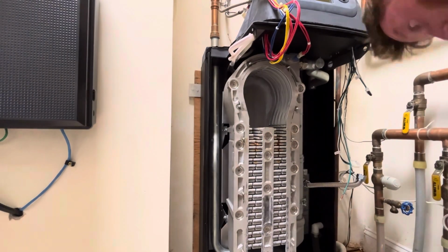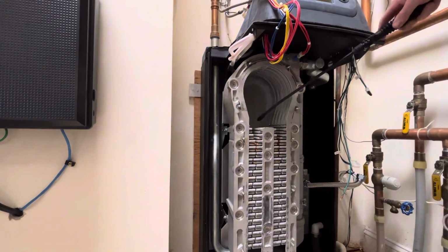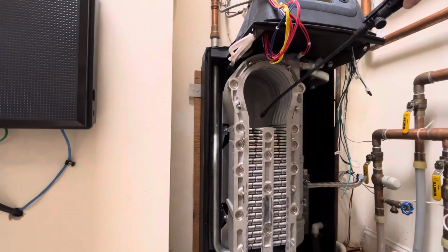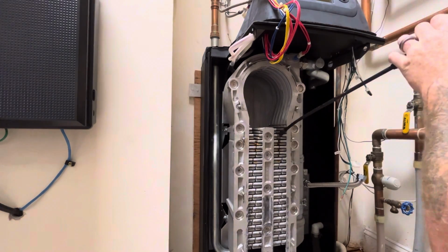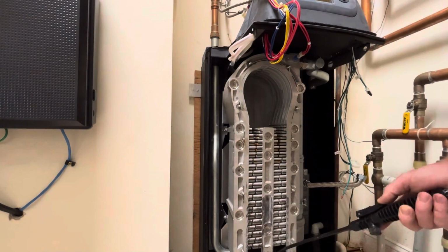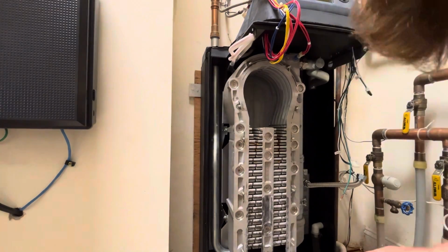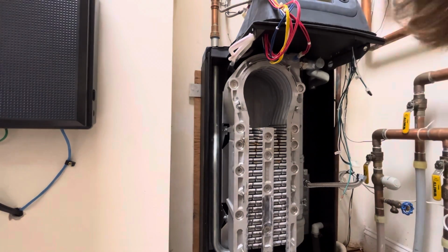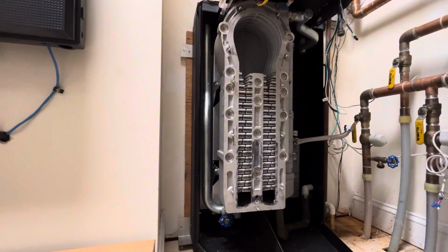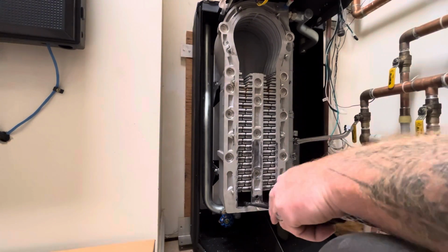This one being less than 5 years old, it says that it does not require tooling, so I'm only going to use water to clean it. The reason that they don't want you to use the tool is because there's a coating on the aluminum that is supposed to protect it from aluminum oxide forming, and apparently that coating is good for 5 years. So basically what they're telling you is that you've got a 5-year heat exchanger.